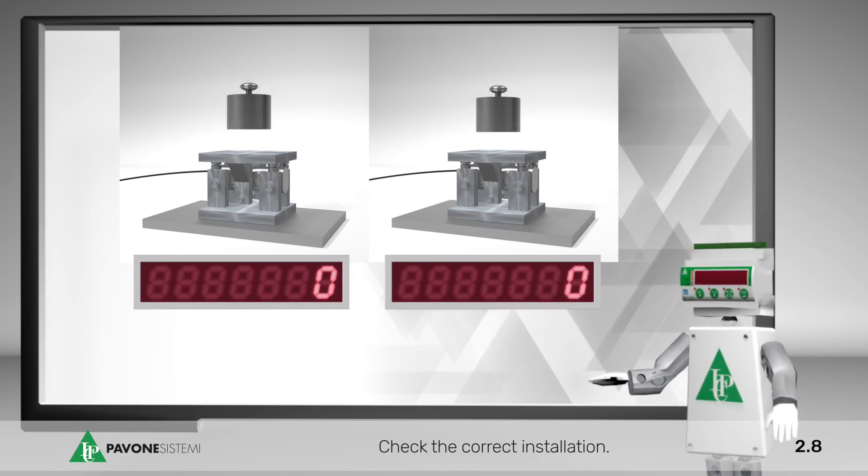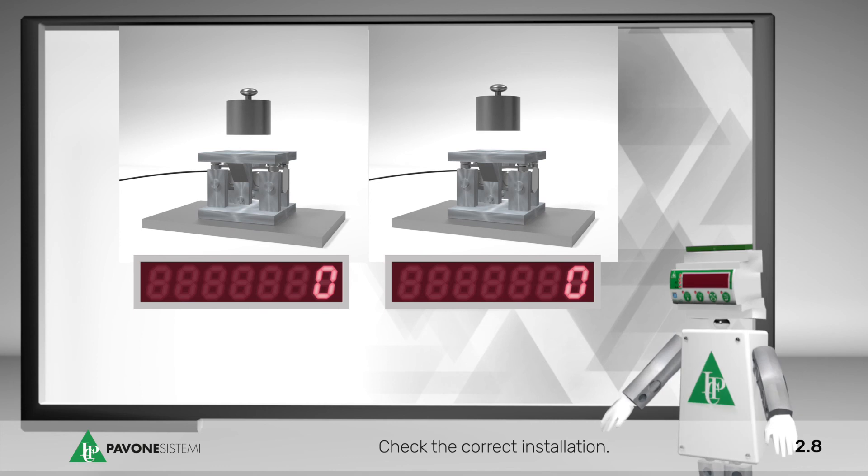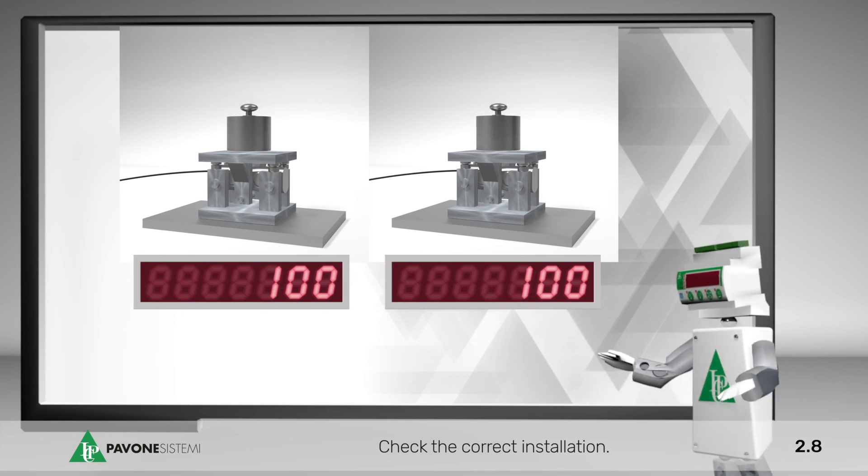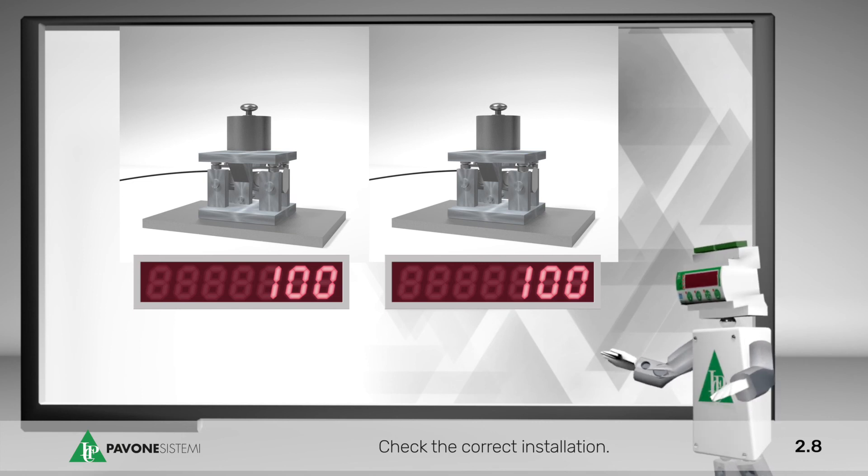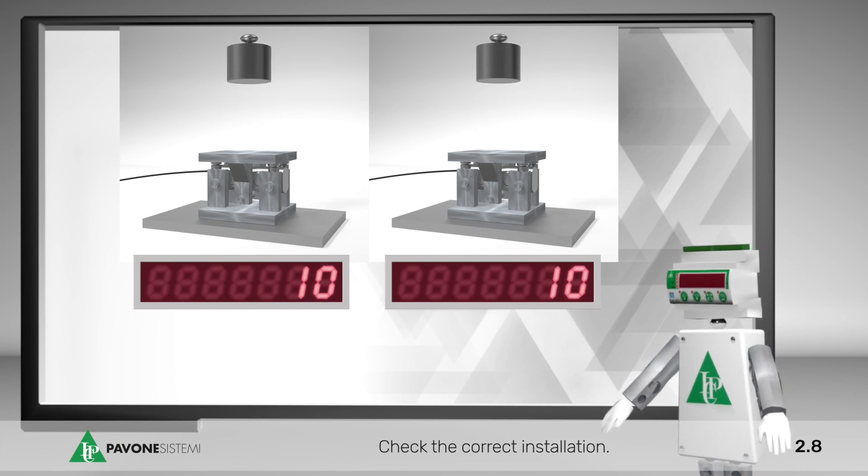In case of a weighing system with several load cells, repeat this operation in correspondence of each load cell. Load and unload each cell, applying a known load and check that the value indicated in the display is steady and repetitive in relation to all points.